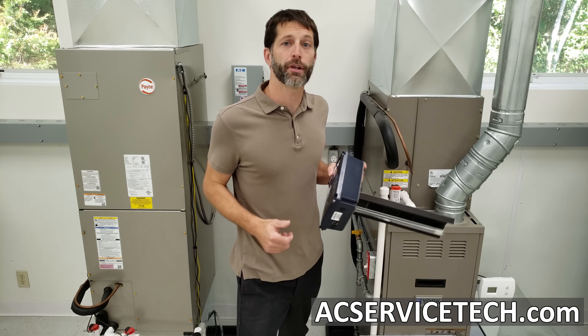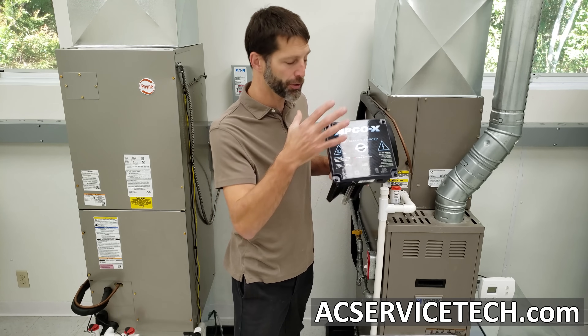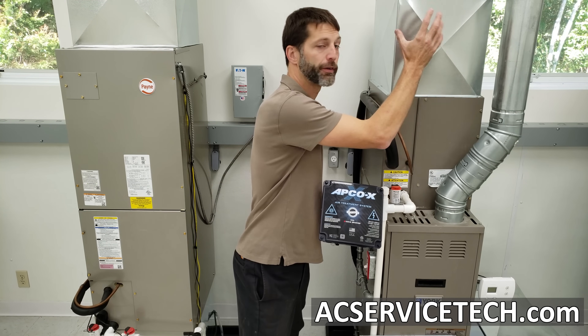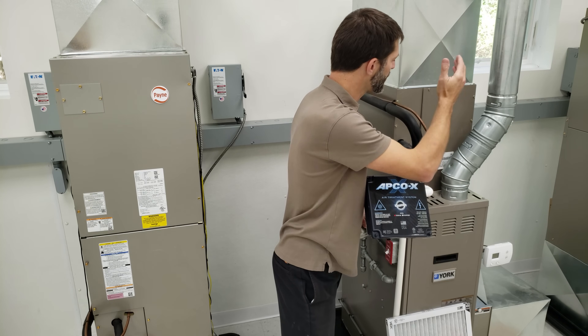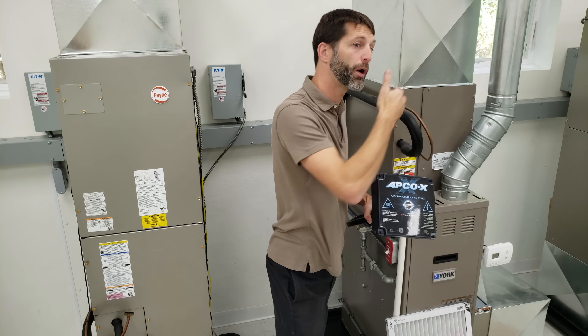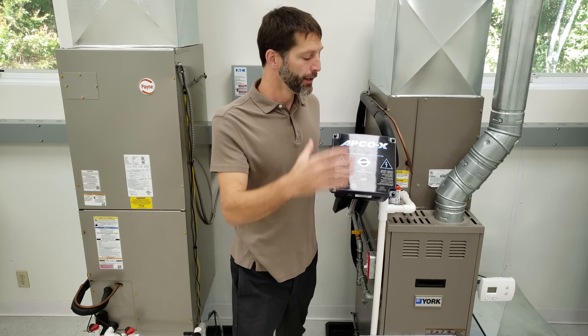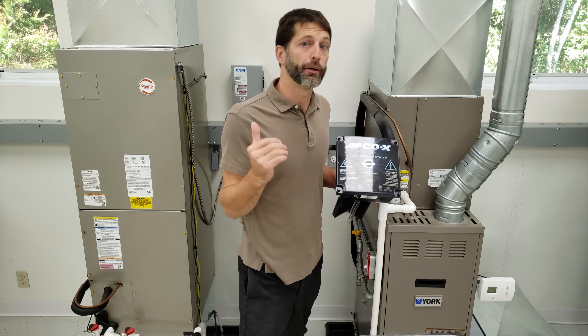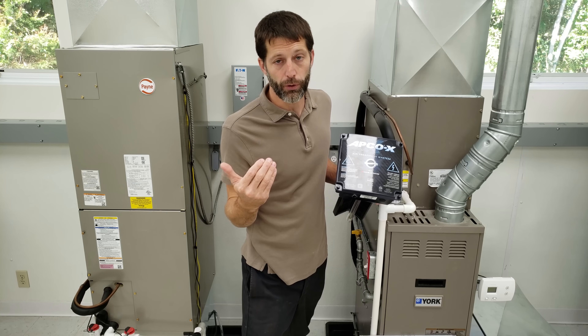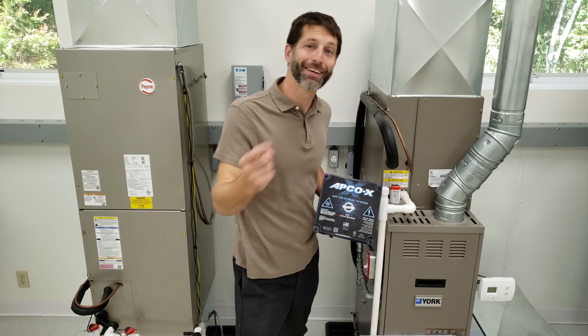This is Craig Migliaccio from ACService Tech and today we're going over the installation of an air treatment system into the supply side of a duct. This is a furnace and air conditioning system and we're going to be installing this step-by-step right into the supply and wiring it in. There are two versions of this Apco X — made by Fresh Air UV — one is a 24-volt model and another is a 120 or 240-volt model.